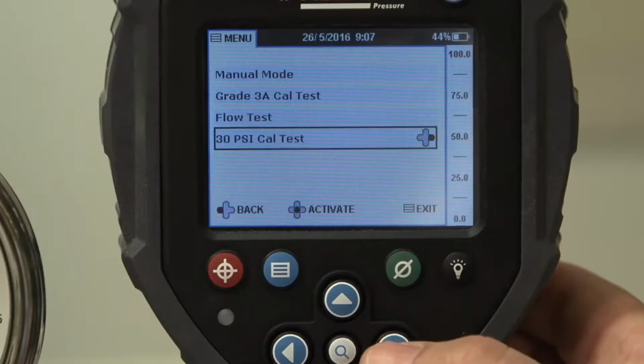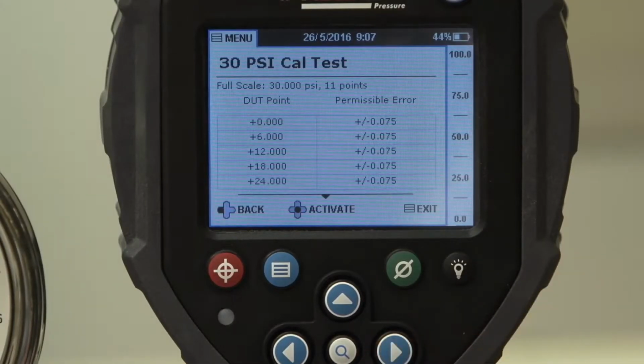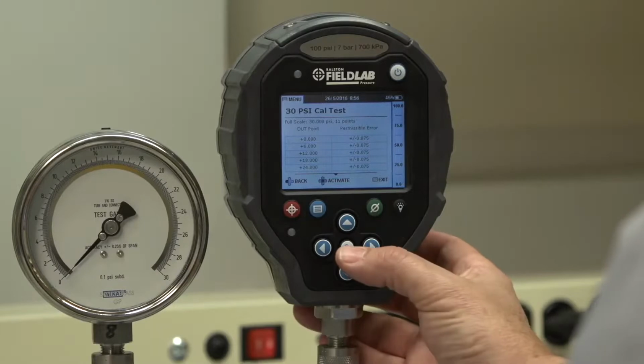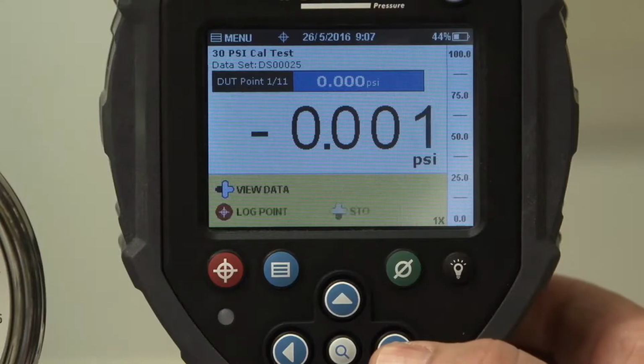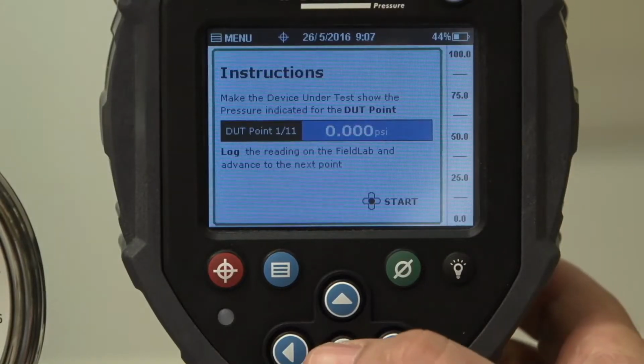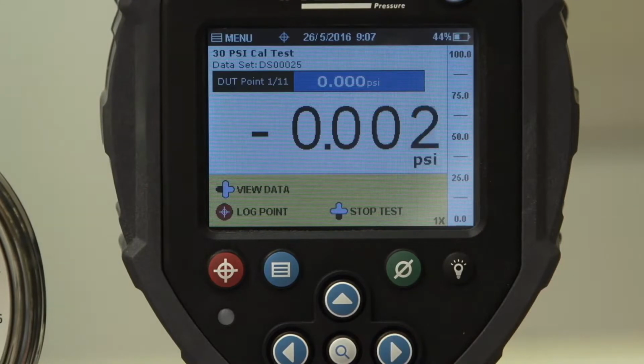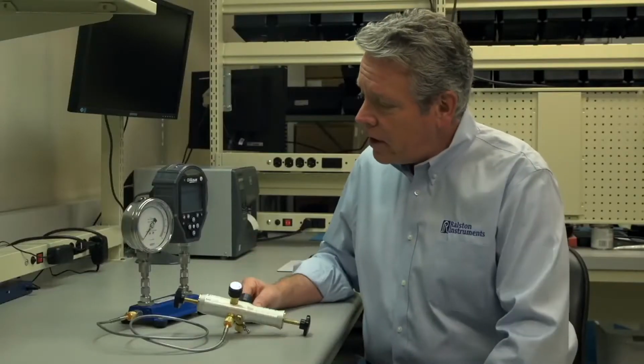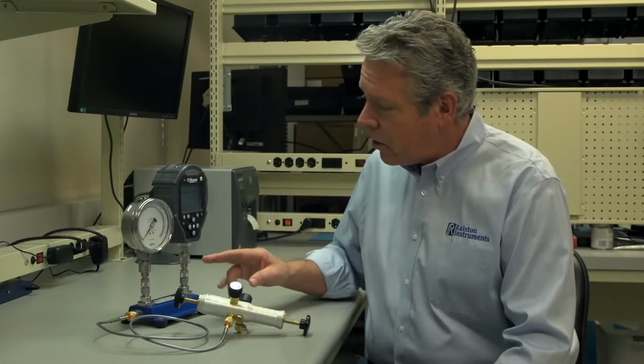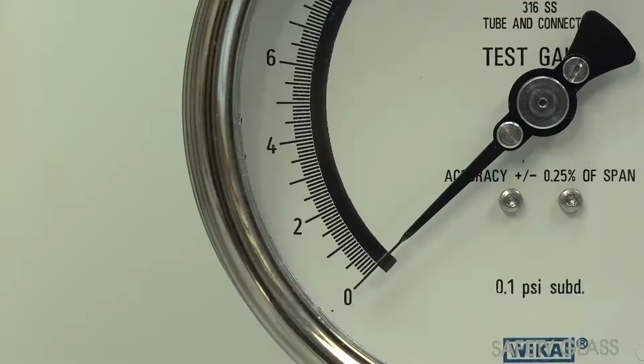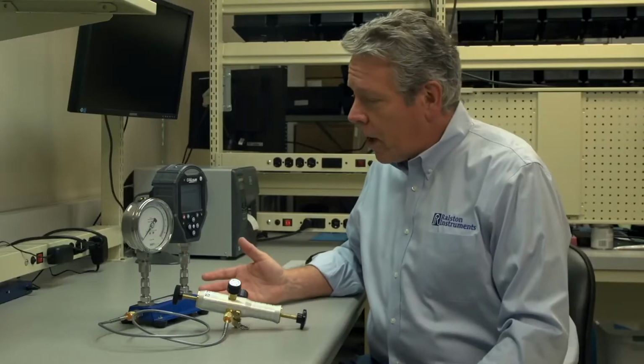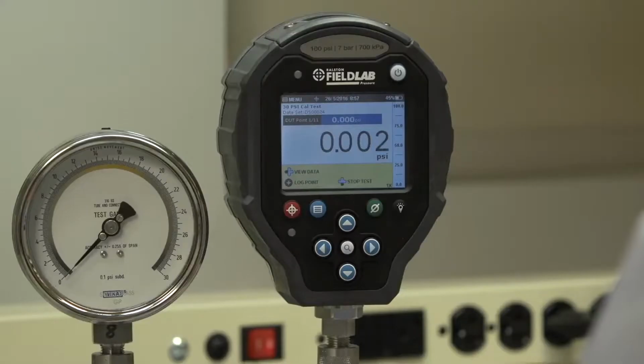So once you select your test mode, you'll see a preview of the number of test points that will be run and the permissible error we expect. Now I'll activate this test mode and start the test. I'm prompted on screen for the first test point, in this case 0 psi. As we can see, our first test point is 0, and with no pressure applied, our needle is right on the 0 hash mark. And since no pressure has been applied yet, the FieldLab also reads 0.